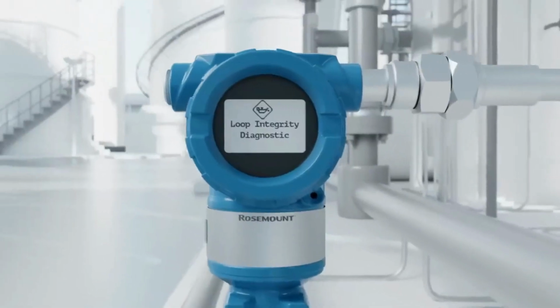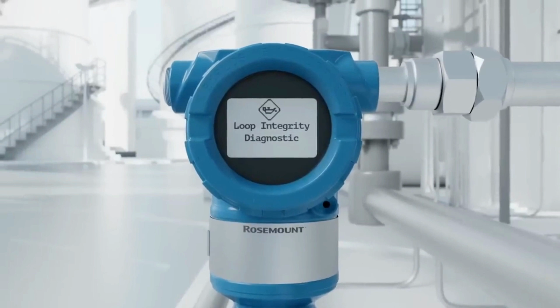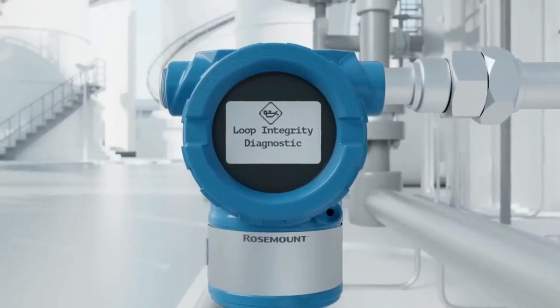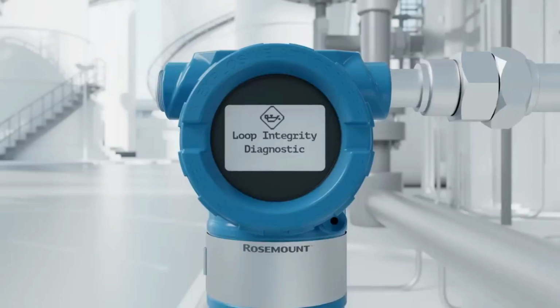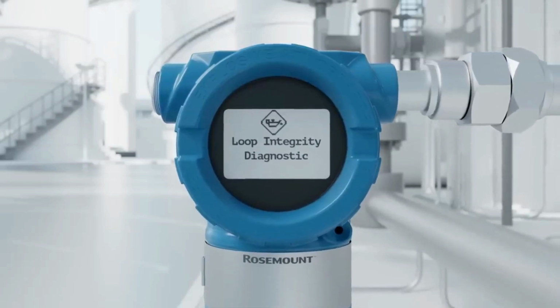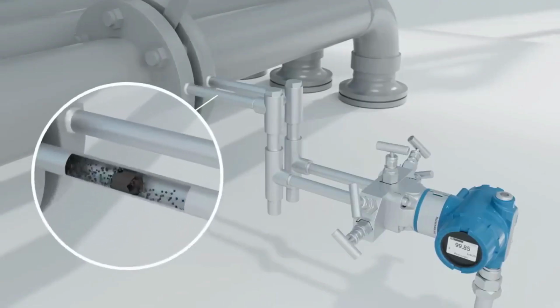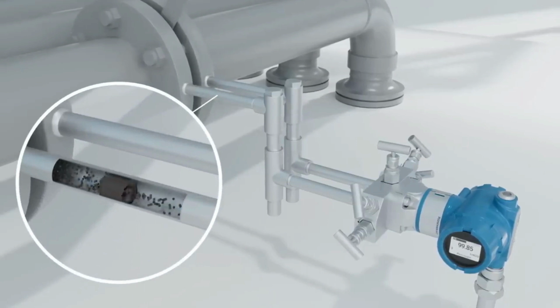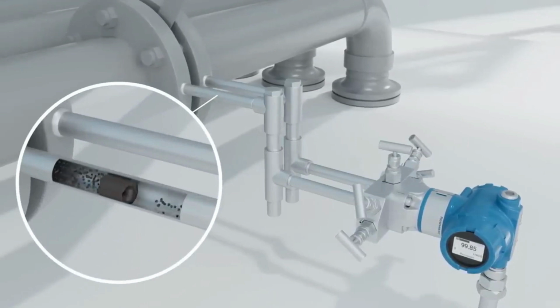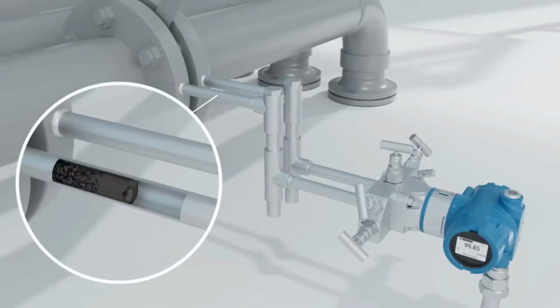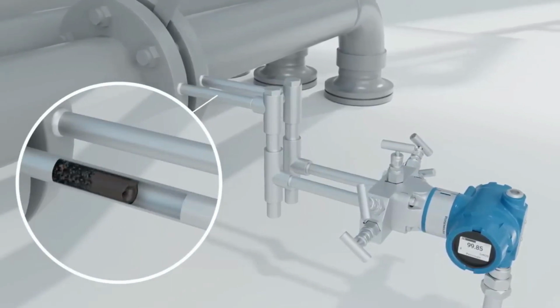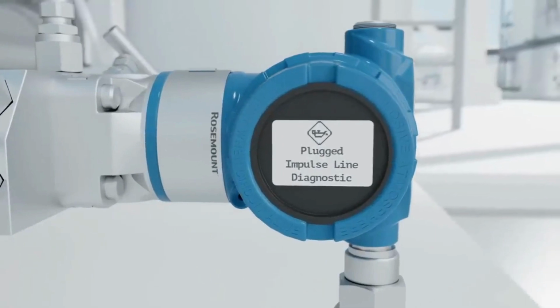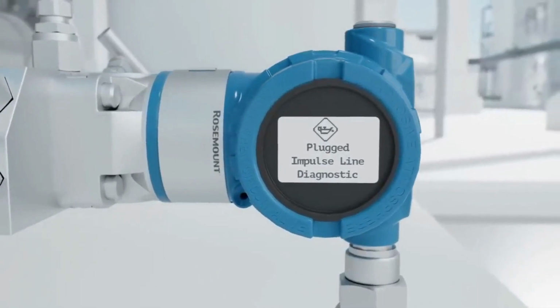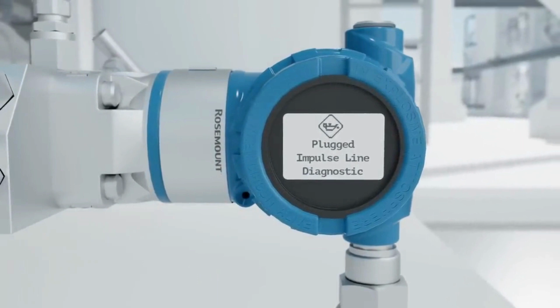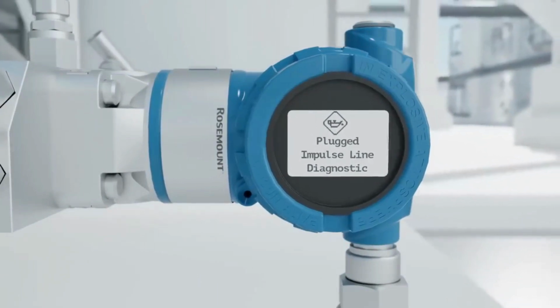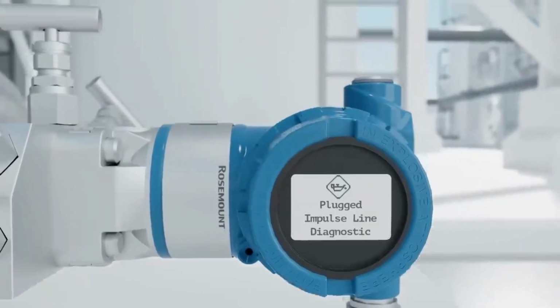The Loop Integrity Diagnostic continuously monitors the electrical loop to detect issues that affect the communication signal and will alert you to corrosion, water in the housing, or an unstable power supply. Impulse piping can be susceptible to plugging from material buildup or freezing, which isolates the transmitter from the process and therefore is unable to respond to process changes. The 3051 continuously monitors for plugged impulse lines and alerts you to abnormal conditions, so you can take proactive measures before it affects the quality of the process.